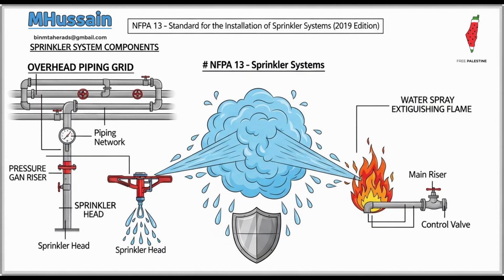Moving to location now. Sprinklers are generally required pretty much everywhere, but there are some critical, recognized exceptions, especially for concealed spaces. Yes, for certain concealed spaces that are deemed low risk, sprinklers can indeed be omitted. A common example is non-combustible, non-accessible vertical duct shafts. If there's nothing in there to burn and no way to actually access the space easily, the sprinkler is considered unnecessary.